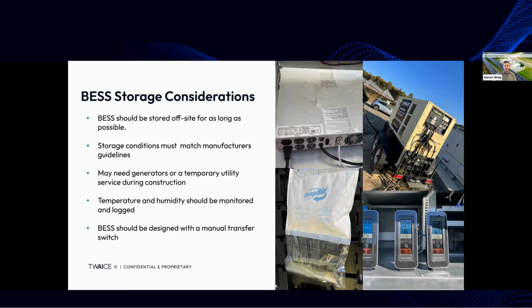For storage, we really want to keep the equipment stored off-site for as long as possible. Ideally it would remain in the control of the OEM. But if it must be moved on site, or you must take control of it, make sure your storage conditions match the manufacturer guidelines, meeting humidity and temperature control requirements.